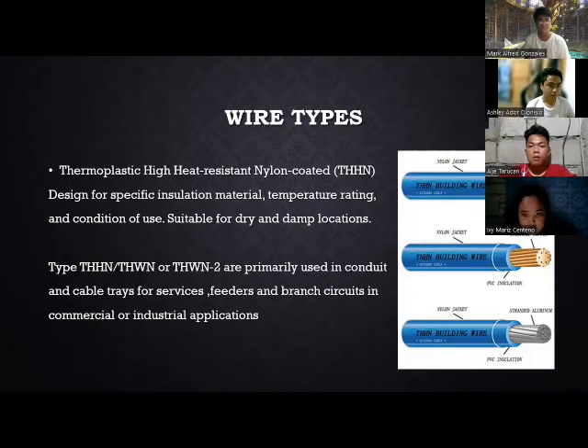Sumunod naman dito ay THHN or thermoplastic high heat resistant nylon coated wiring, designed for specific insulation material, temperature rating, and condition of use, suitable for dry and damp locations. Type THHN or THWN or THWN2 are primarily used in conduit and cable trays for services, feeders, and branch circuits in commercial or industrial applications. Ito na nga, yung mga pang malalakihan na pang industrial. Kanina yung mga TW, THW, mga pambahay lang yan. Ito mga THHN o THWN, mga pang business na yan.